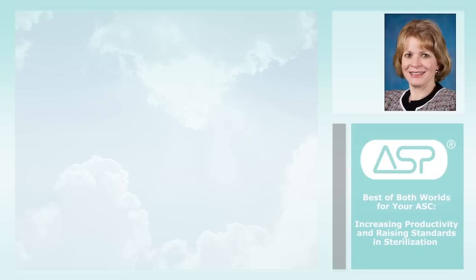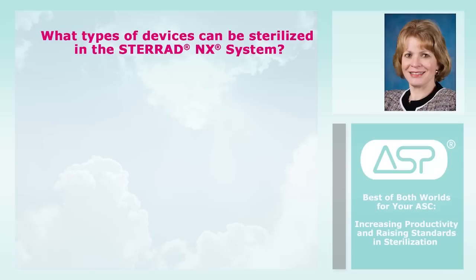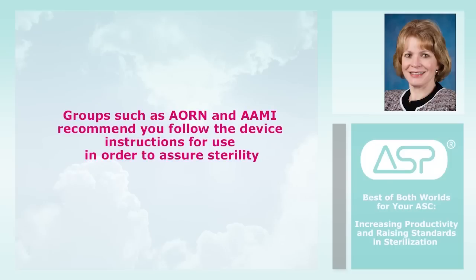Another common question we received is, what type of devices can be sterilized in the STERRAD NX system? We always remind our customers that when you invest in new medical devices or sterilization equipment, you must follow the medical device manufacturer's instructions for use to determine if the device is validated for a specific sterilization system. Both AORN and AAMI recommend you follow the device instructions for use in order to assure sterility. And as Kathy mentioned previously, it is important you know that not all devices cleared for reprocessing in the SS1 are cleared for reprocessing in the SS1E.